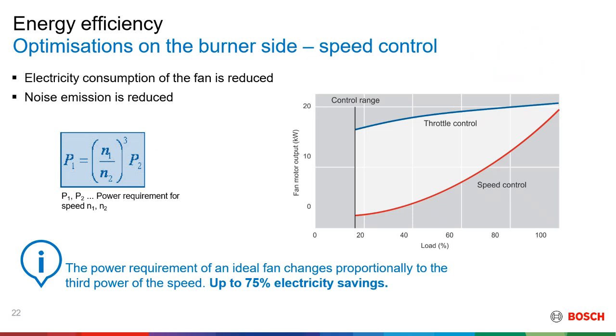Okay. So on the first topic, speed control. In most scenarios, you will have a burner that has a motor which is driving a blower fan. Usually, most burners will not have speed control. What does speed control do? Speed control will match the air demands of the burner to the speed of the motor. Therefore, you're able to get the correct amount of air depending on the burner load.